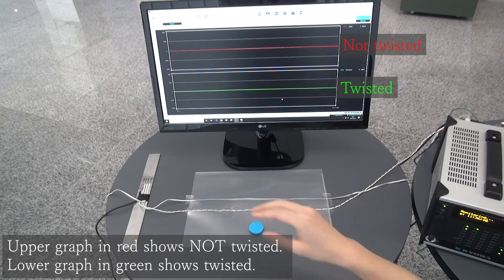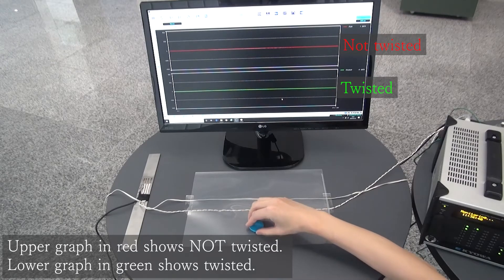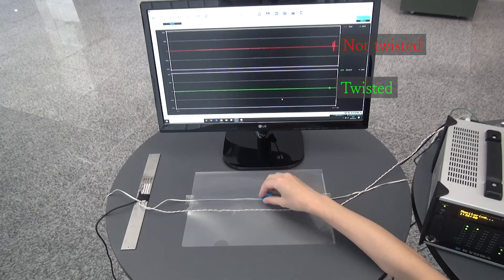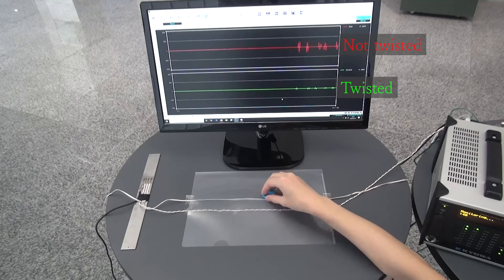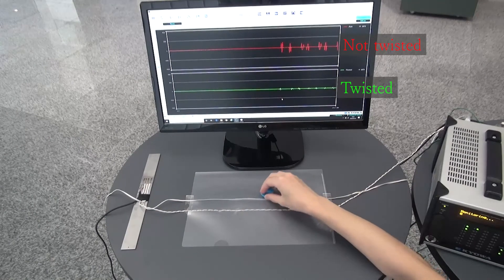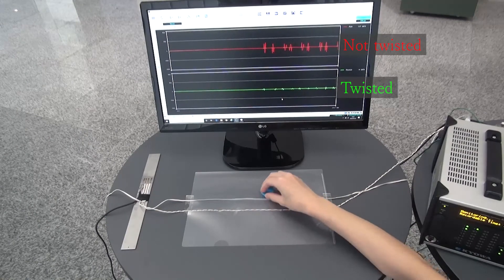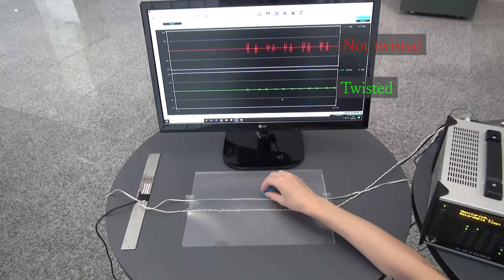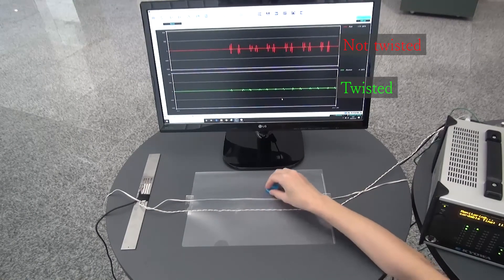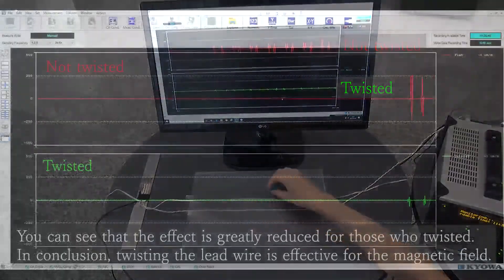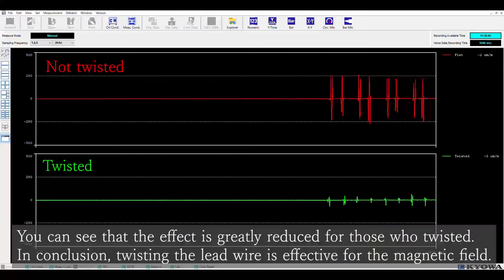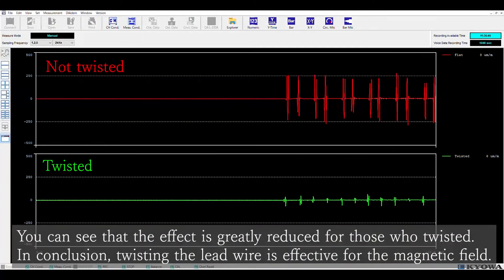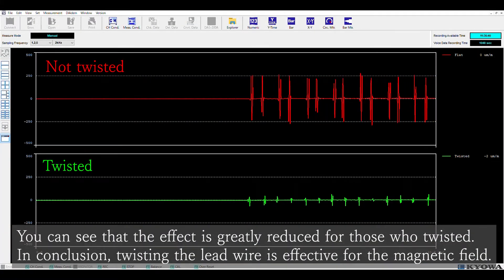We are preparing a magnet and move it on the lead wire of the gauge to change the magnetic field range. As you can see on the monitor, the effect of the magnetic field is greatly reduced by twisting wire.